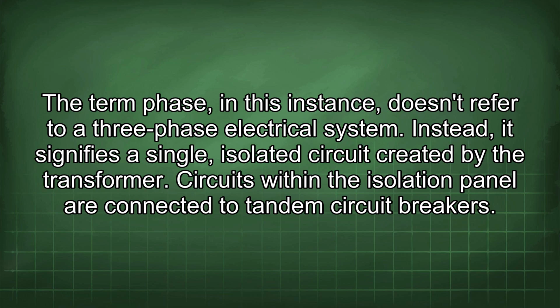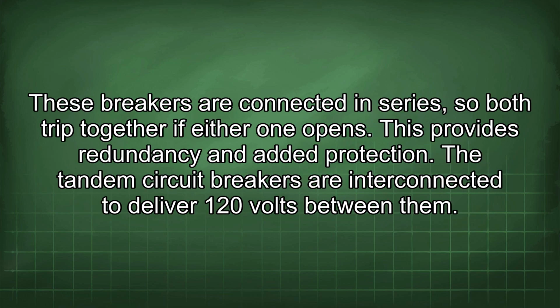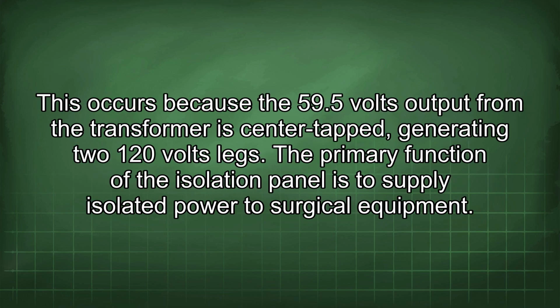Circuits within the isolation panel are connected to tandem circuit breakers. These breakers are connected in series, so both trip together if either one opens. This provides redundancy and added protection. The tandem circuit breakers are interconnected to deliver 120 volts between them. This occurs because the 59.5 volts output from the transformer is center-tapped, generating two 120 volts legs.